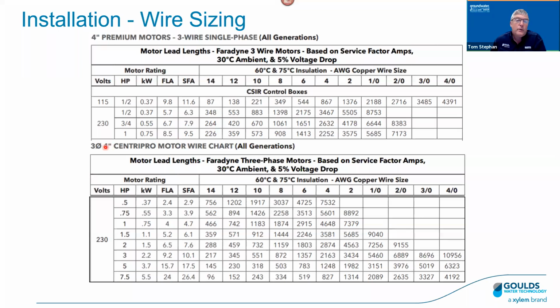So let's compare that a little bit to 3-phase. Same chart in terms of the way it's laid out, but we're looking at a 3-phase motor now. Let's do the same comparison, half 230 3-phase, 14-wire, 756. So the bottom line there is with 3-phase, I can use smaller wire. And why is that? Well, it's all about amperage, right? Compare the amperage of the 3-phase motor, and let's look at service factor amps. The half 230 3-phase is 2.9 versus 6.3 for the single phase. So that's why those wire charts are different. And that's one of the big advantages that we have with a drive. Most drives require a 3-phase motor, right?